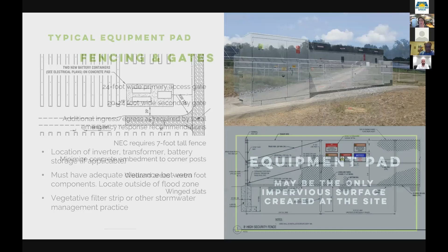Regarding fencing and gates, we want feedback from the fire chief and emergency responders about what's appropriate, but at a minimum we think a 24-foot wide primary access gate is necessary, ideally with a 20 to 24-foot wide secondary gate elsewhere within the fence line, plus any additional ingress or egress required. Some places require man gates at certain spacing so people can exit in an emergency. The National Electrical Code requires a 7-foot tall fence, which will probably be the minimum height you'd expect to see, and that may conflict with existing zoning codes.